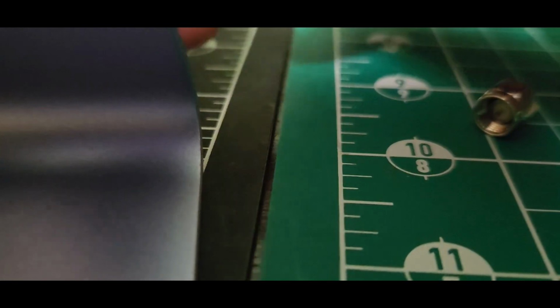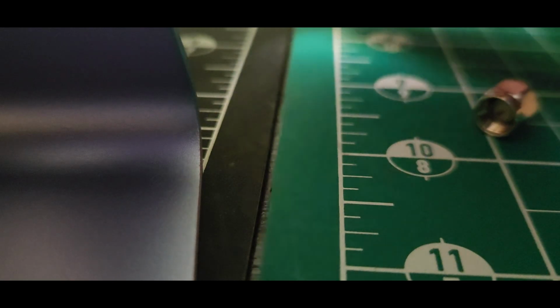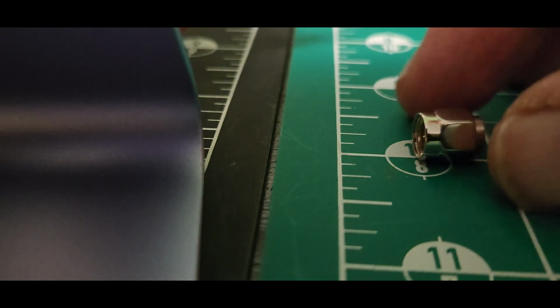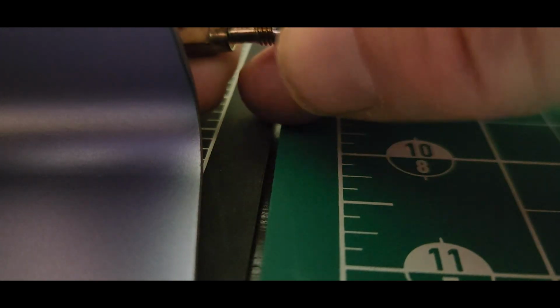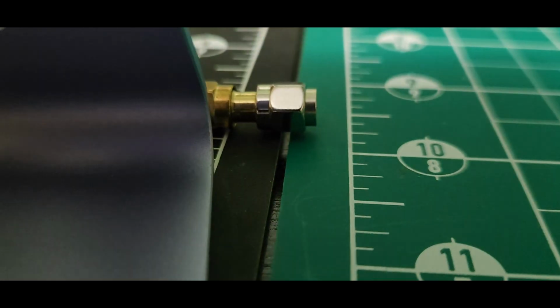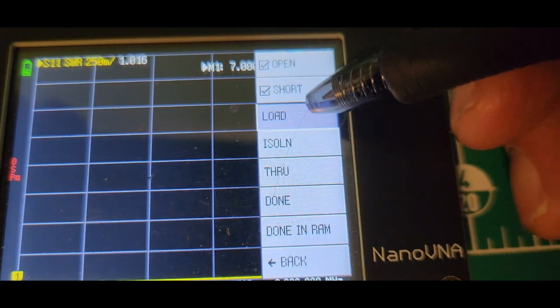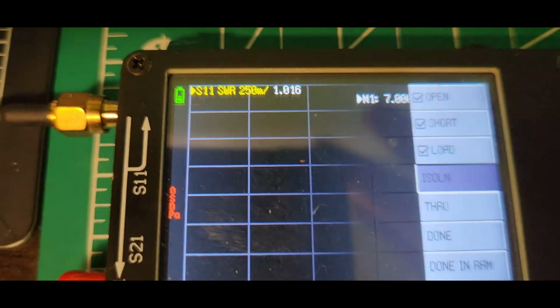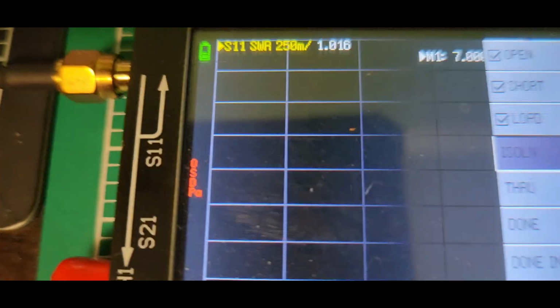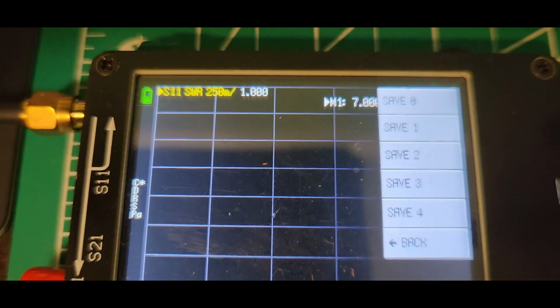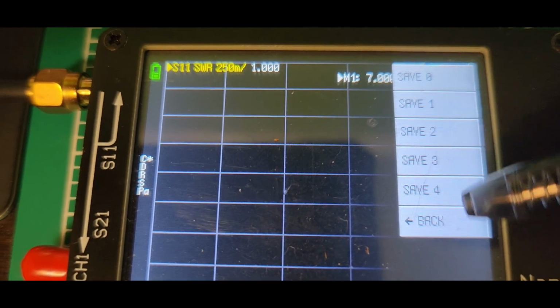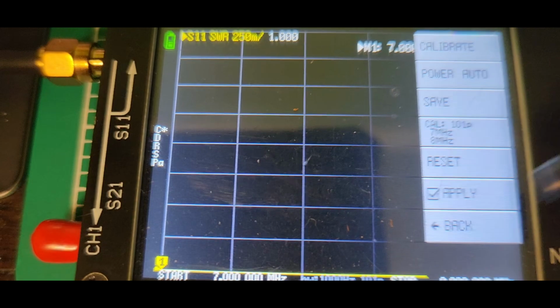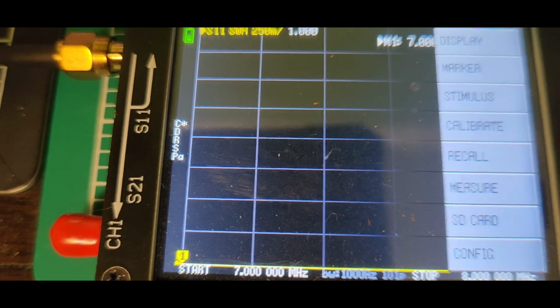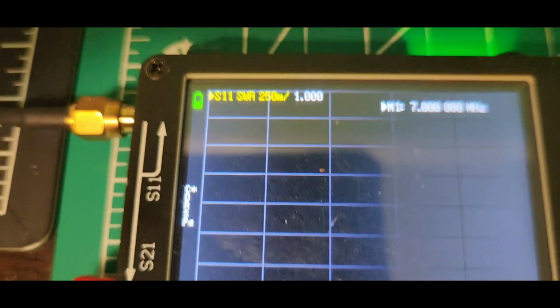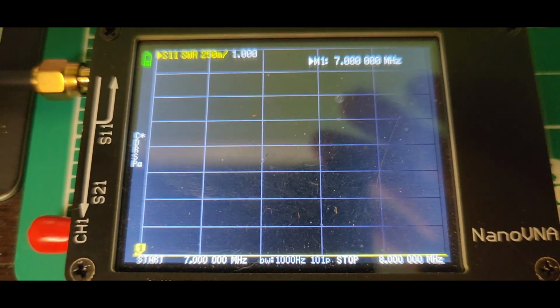And finally, we place the 50 ohm load on our SMA barrel connector, tighten it, and run the final test for the calibration we need. Okay, so we won't be needing isolation or through, so we can now click done. So normally we would save this. I'm going to just go back and not save, and back again. All right, so we're ready to run the test.